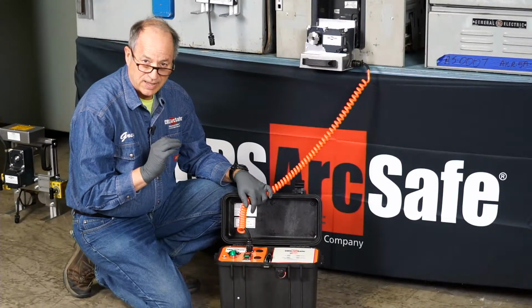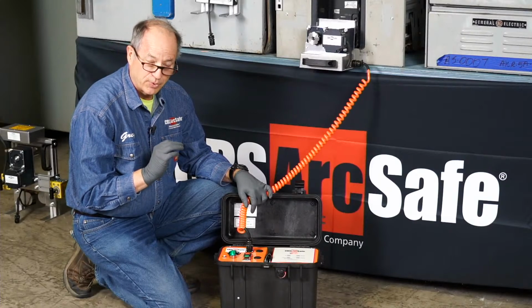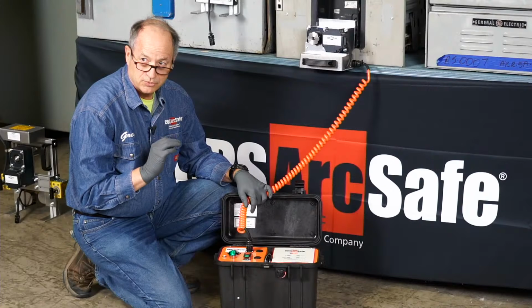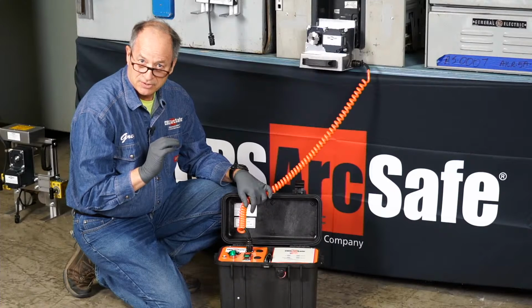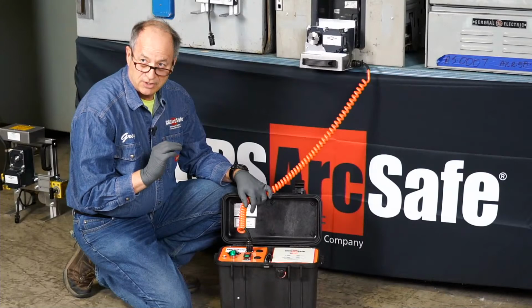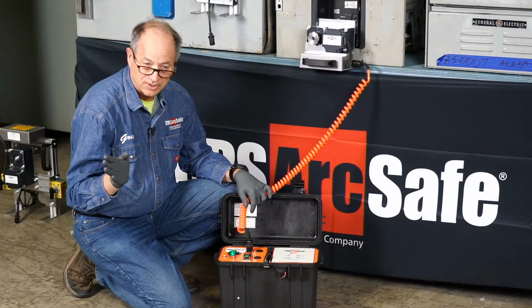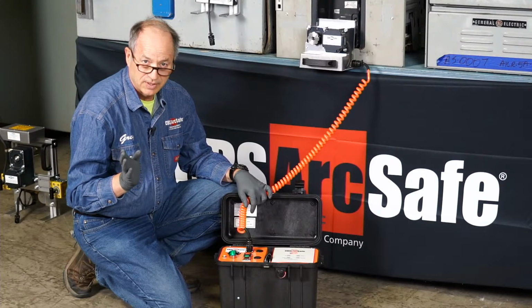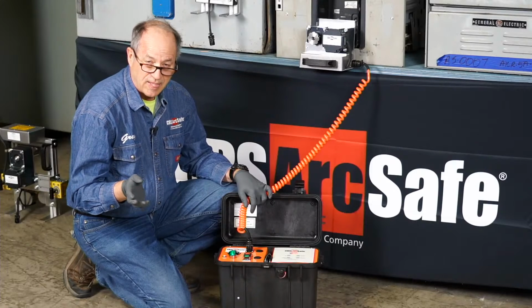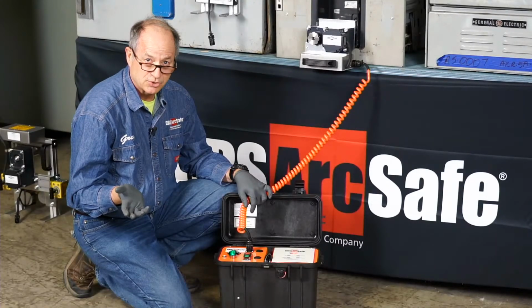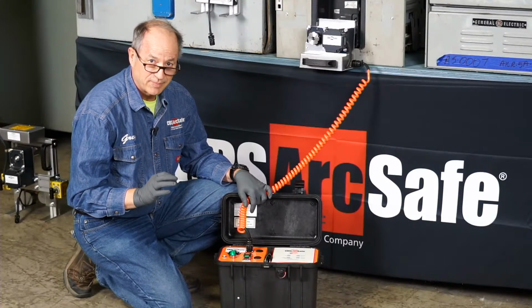Just one thing to note, up until about 2012, no manufacturer ever put the force required to rack their circuit breakers in any manual. ABB was the first one I saw with their VD4 switchgear, and then Schneider with their MCset, and following that shortly after, the Masterpacts in about 2012, 2013, were the first switchgear manufacturers that actually put that in there. If you looked at anything 2010 or earlier, they just looked at it as an additional warranty item they didn't want to worry about until you, the customer, demanded that information. Then finally the switchgear manufacturers started giving it to you. But prior to 2012, that information was in no switchgear manual you could go look at for any manufacturer.